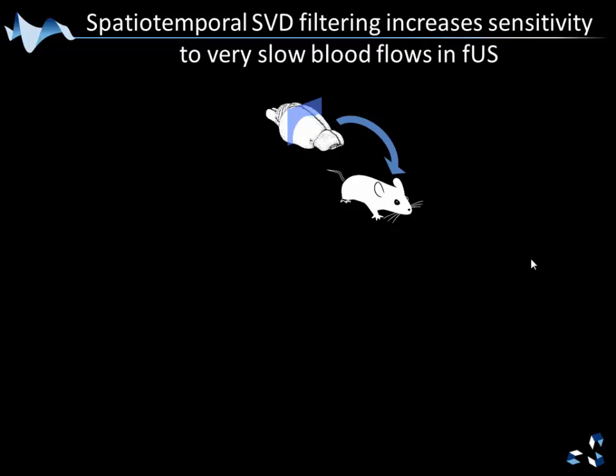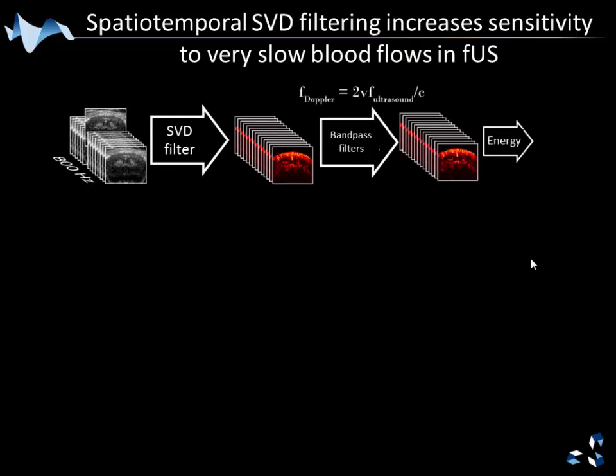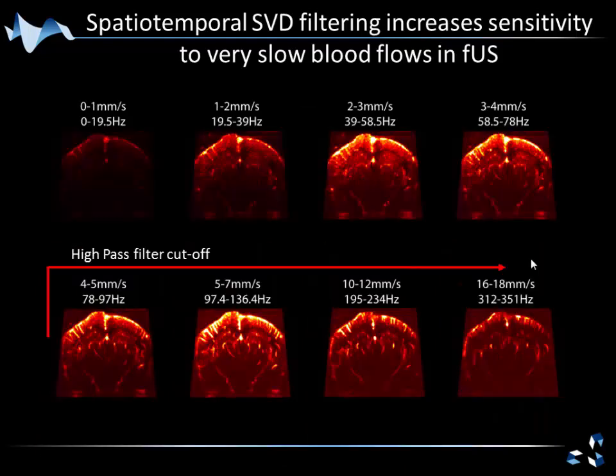This has huge implications for functional imaging. Taking the rat brain with an ultra-fast Doppler recording, filtering with the SVD filter, and selecting different speed bands with a band-pass filter, I can collect energy for blood flow speeds as low as 1 millimeter per second. That would not have been possible with a high-pass filter, because to eliminate the tissue I would have to set the cutoff frequency at least at 60 or 70 Hz, losing everything below that. This is critical because we want to detect slow blood flow in arterioles and venules where neurovascular coupling occurs.